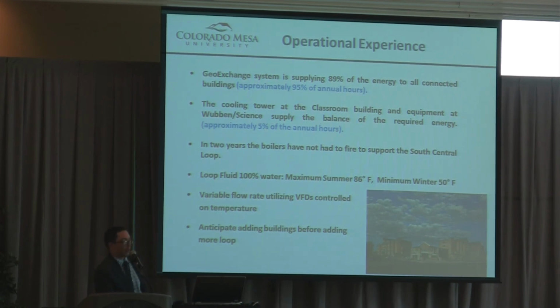So at this particular system, as I mentioned, the boilers have not had to fire. About 89% of the energy in the system is coming from either energy recovery from building to building or from the geothermal system. The balance is coming from the fluid coolers.